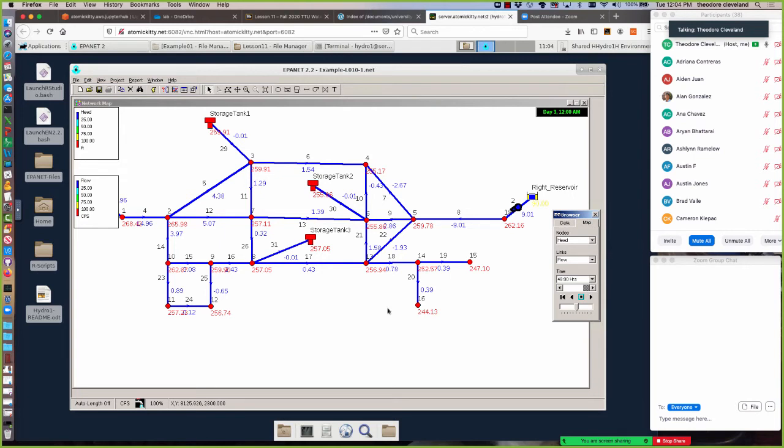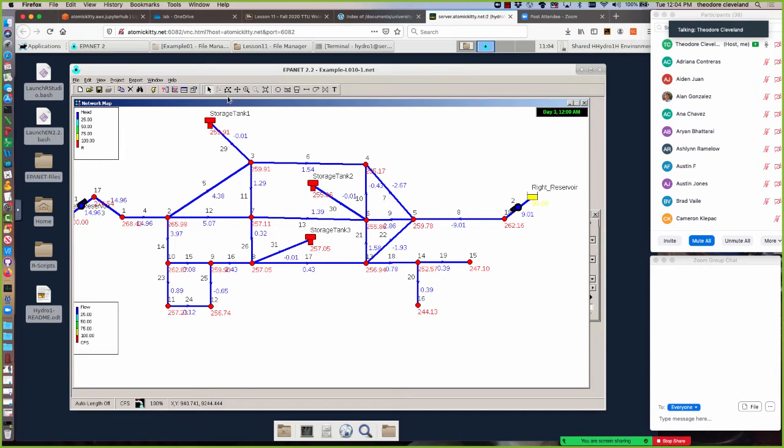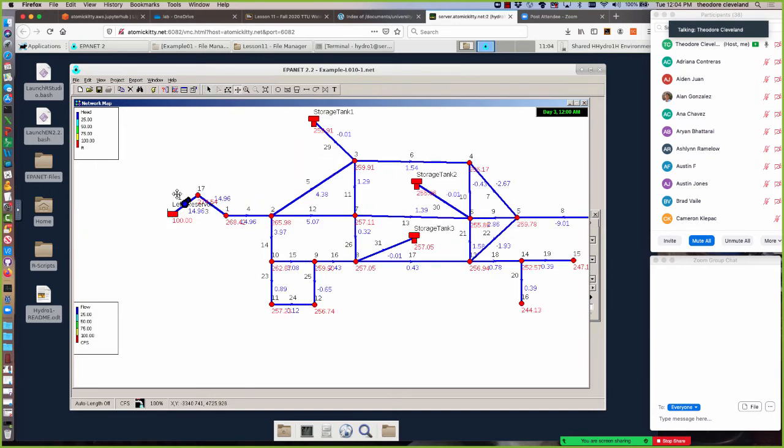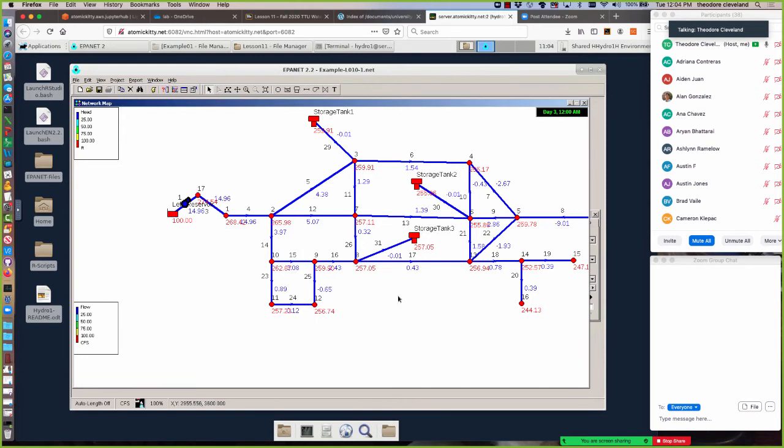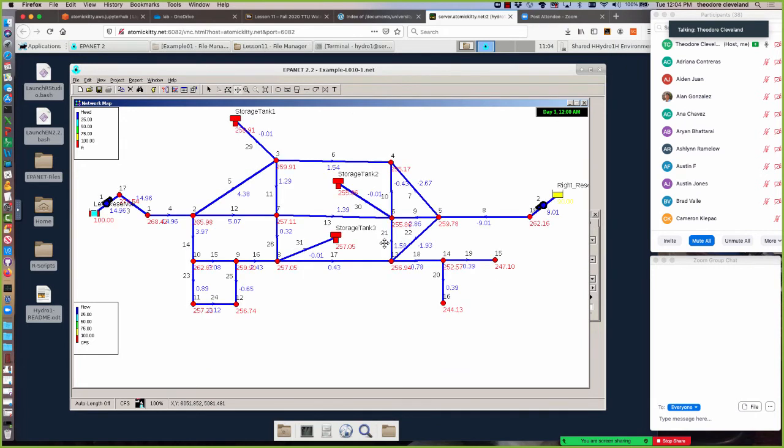That's getting somewhere. So we drop that into the 90s. So I'm going to do the same on the left reservoir if I can find it. Naturally, it is off scale because... So effectively what I'm doing by reducing the reservoir elevations is I'm forcing the pumps to move at different points of their pump curves, and that's going to have overall effect on the entire network. So I run that. What I'm trying to do is get them low enough that this thing cycles.